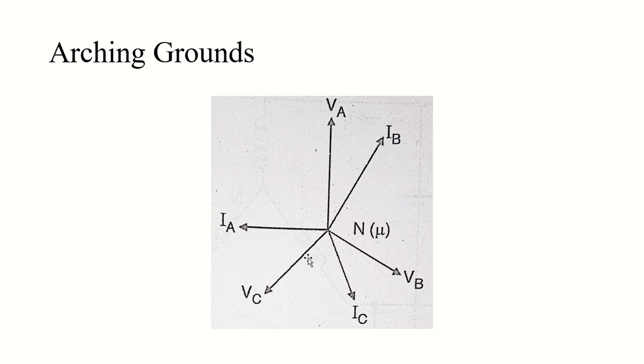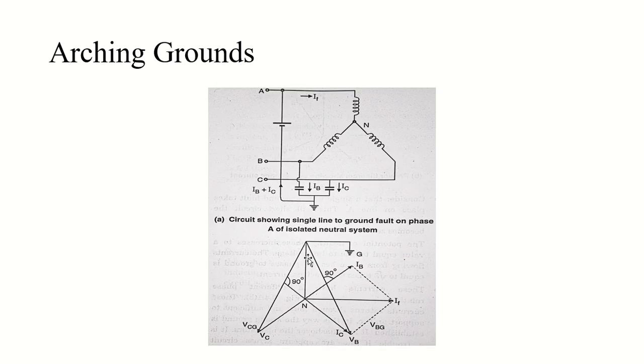You can also see this in the phasor diagram. IA, IB, IC and VA, VB, VC were very different. In the phasor diagram you can see VC, VB, VA — the fault is occurring at VA so VA will be zero because it is short-circuited. Here is your fault current IF, here is your IB, connecting them we will have VGC, here is your IC. The neutral is not being grounded in this configuration.